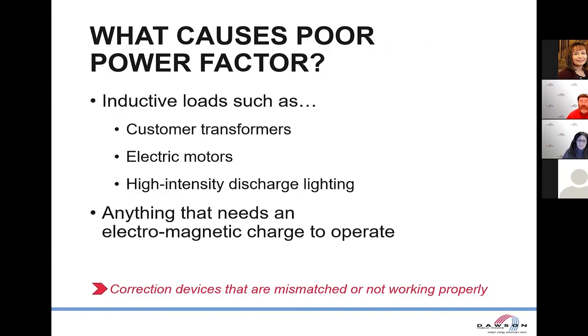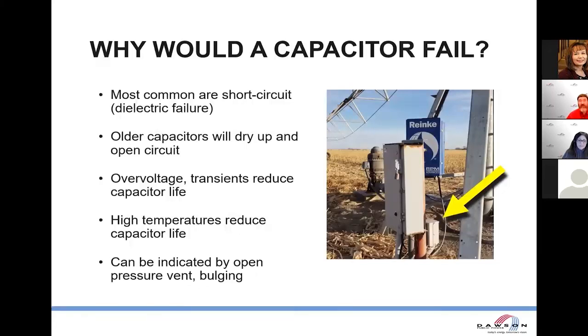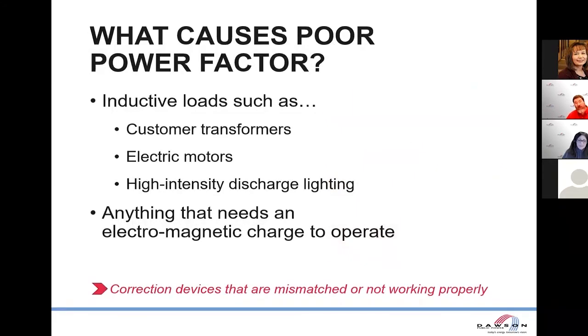If you've got a correction device that's overcompensating, so it's putting you over 100%, that also could potentially be affecting your power factor. Basically, if your capacitor is way too large for the motor it's paired with.